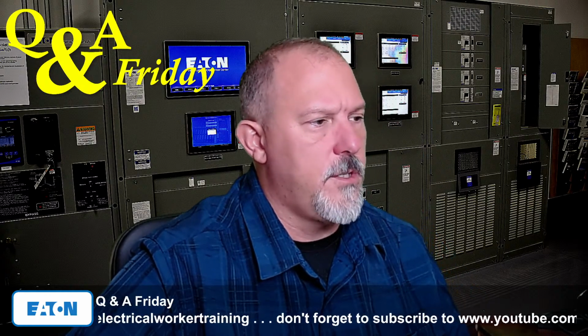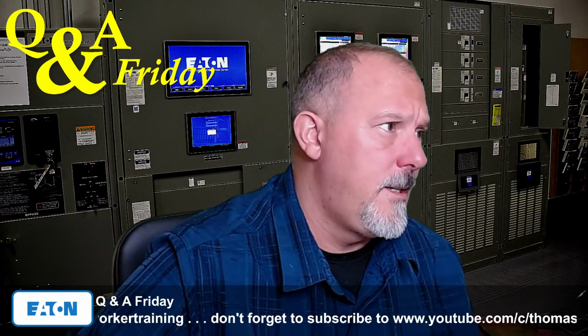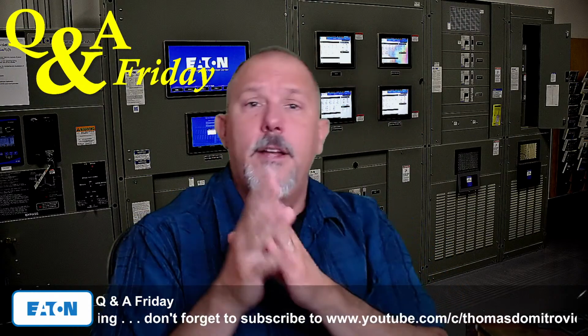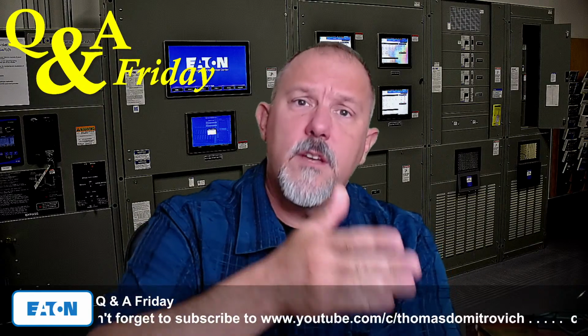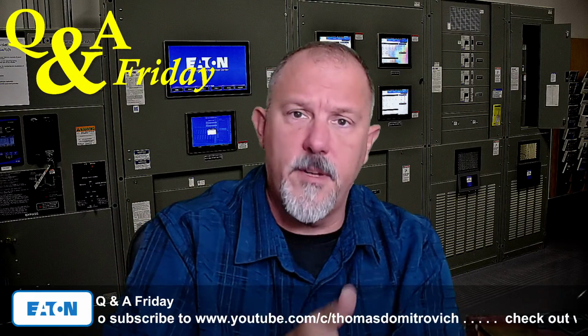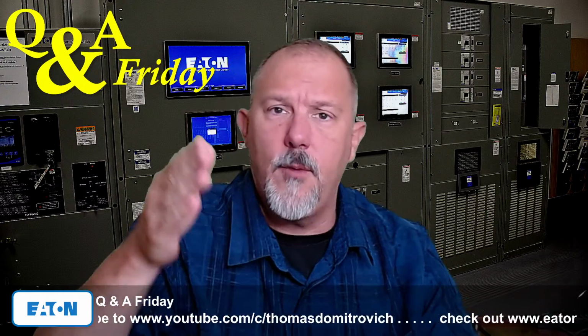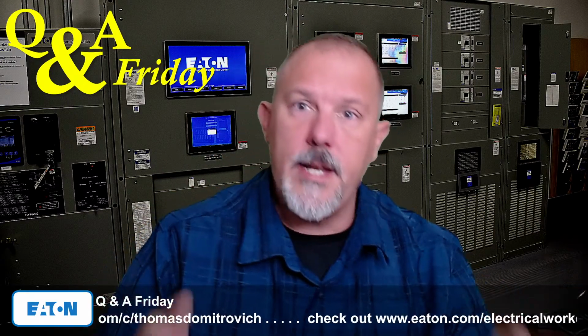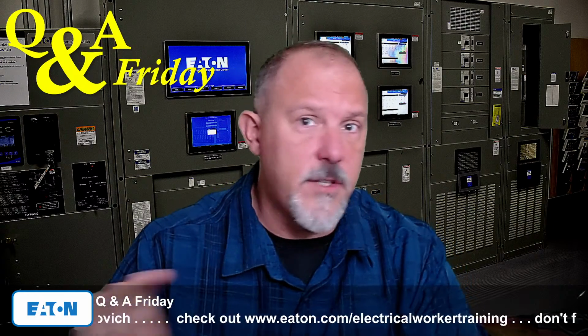Restricted earth fault protection. Here's my thought process. We know that Article 450 has the requirements for transformer protection. We have primary and we have secondary, and it tells us when we can do primary only and when we need primary and secondary protection. And there are other references in there as well.